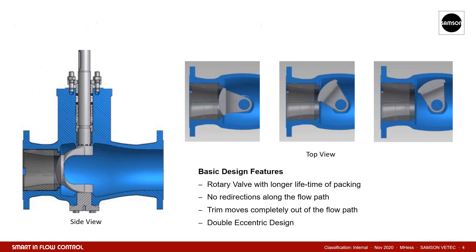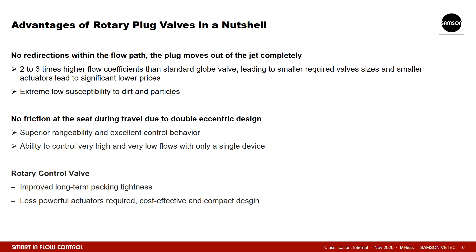There are three major advantages of rotary plug valves. The first is the free flow path without any redirections, combined with the fact that the plug moves out of the jet in the fully open position. Rotary plug valves have a two to three times higher flow coefficient compared to standard globe valves. Thus, smaller sizes and smaller actuators can be utilized for identical process conditions, leading to a significant price reduction. This physical background also leads to an extremely low susceptibility to dirt and particles. The second advantage is that due to the double eccentricity, there is no friction on the seat during the plug's travel. Rotary plug valves therefore have excellent control behavior and superior rangeability, making them a first choice when very high and very low flows need to be controlled with only one device.